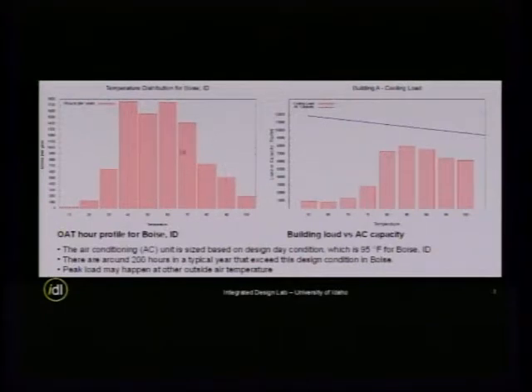Which is representing many, many hours throughout the year. But we know during this hour, during this outside air temperature, we have a capacity that is way too high compared to the building load. So the air conditioning will operate on probably 30% or 25% of its capacity. This is what it's called, they are running on a part load condition. So when they run at the part load condition, they become less efficient.